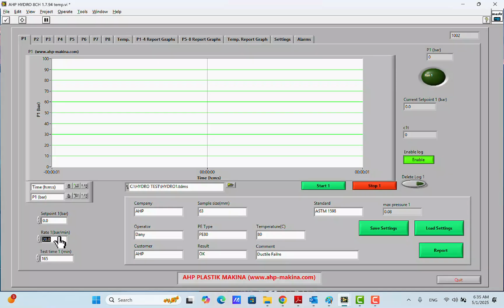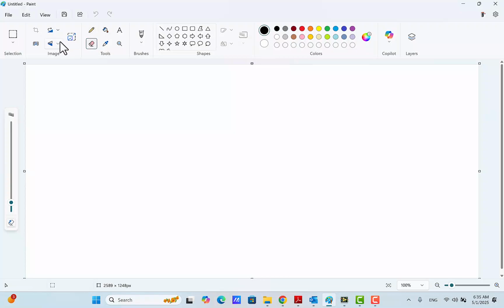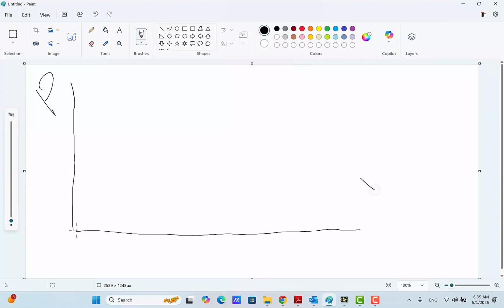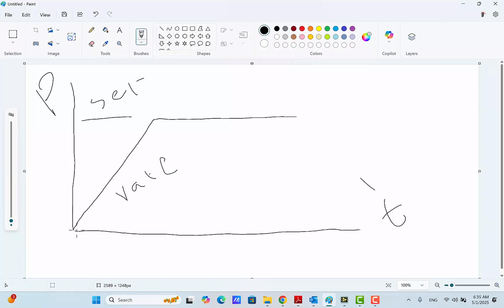Rate is the pressure increase rate. Suppose that you want to set the pressure. This is the pressure I'm showing you here. Suppose that you want to increase the pressure like this. This is pressure, this is time. You want to increase the pressure like this slowly to get to the set point. Set point is here. Rate is the pressure increase rate that is shown here.